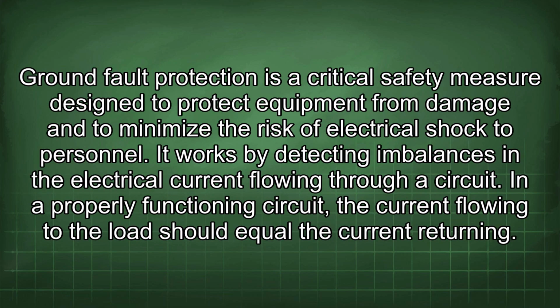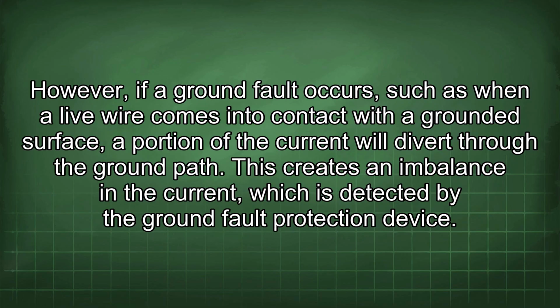Ground fault protection is a critical safety measure designed to protect equipment from damage and to minimize the risk of electrical shock to personnel. It works by detecting imbalances in the electrical current flowing through a circuit. In a properly functioning circuit, the current flowing to the load should equal the current returning. However, if a ground fault occurs, such as when a live wire comes into contact with a grounded surface, a portion of the current will divert through the ground path. This creates an imbalance in the current, which is detected by the ground fault protection device.